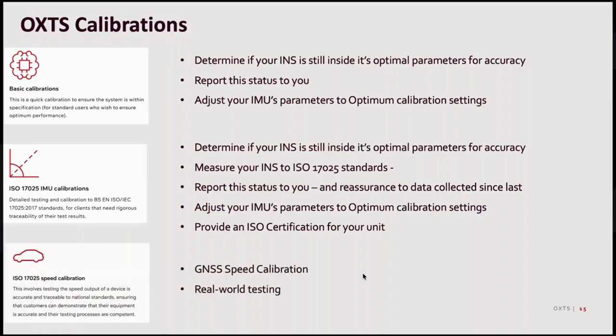And finally, the new service that we started providing just a few months ago is a speed calibration. In this case, what we're doing is calibration based on what speed our device is telling you that your unit is traveling at compared to a real world testing situation. There are other companies that do offer this, but we're in a very small subset of companies that offer that. And within that, some of them do provide simulated results. We decided that it was important and provided better information to do real world testing. So when we're measuring the speed measurement compared to the real world speed conditions, we're actually doing that in a car on a track, real world conditions, to high accuracy.